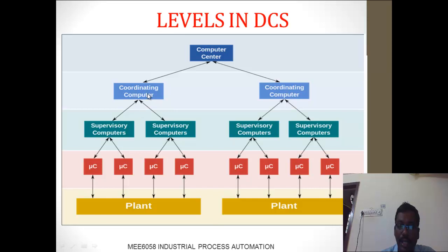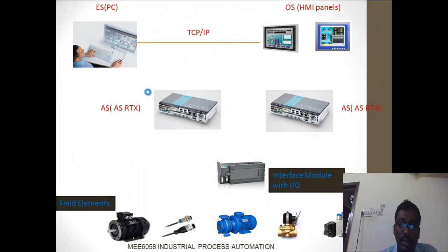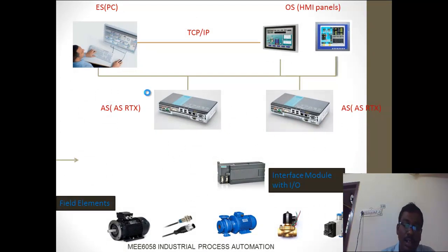The operator station can monitor what is happening in process one, but it does not have the rights to enter the program or modify the sequence. If I want to change or control the process, I do not have the rights to do so from here. The order comes from the engineering station, and the data is transferred here. The operators are only observing and cannot modify or alter the programs or sequence. So here you can find the engineering station and the operator station.